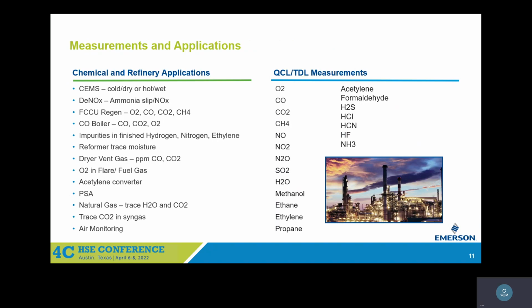On the right-hand side are the measurements that we make. And on the left-hand side, I just threw up some chemical and refinery applications that we do outside of CEMS, but we do a lot of CEMS, a lot of DeNOx as well, looking at ammonia slip, as well as NOx after SCR. But things like looking at the off gas from the FCCU regen, looking at impurities in hydrogen, et cetera. So there's a number of different things that you see there outside of CEMS. But the measurements that you see, O2, CO, CO2, NOx, SO2, water, even HCl, HCN, HF, and ammonia, those things apply to emissions monitoring.